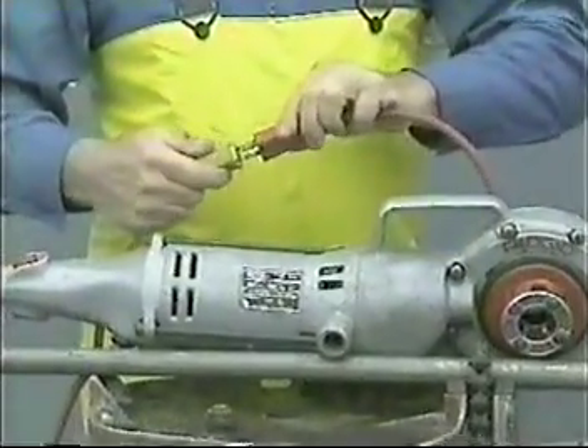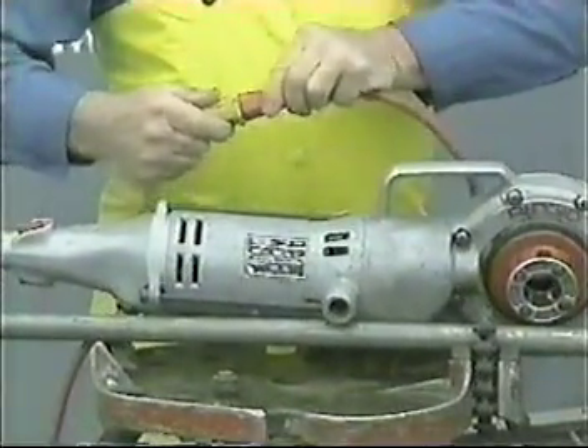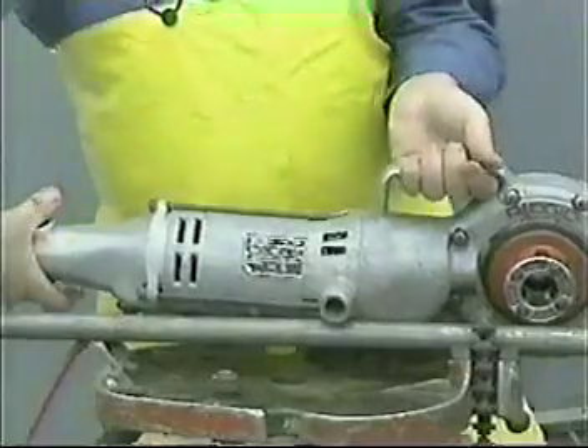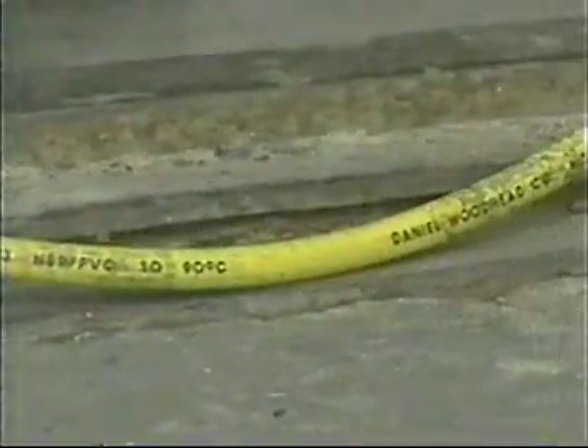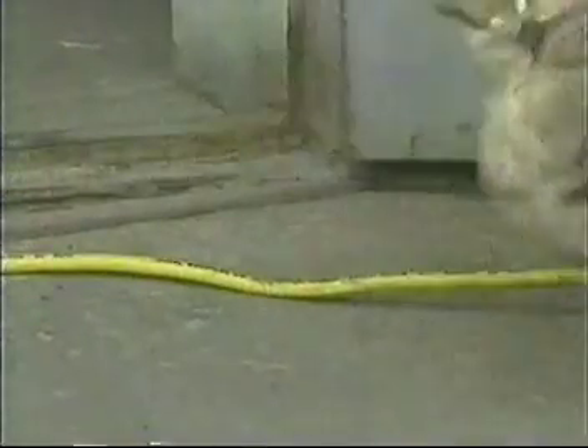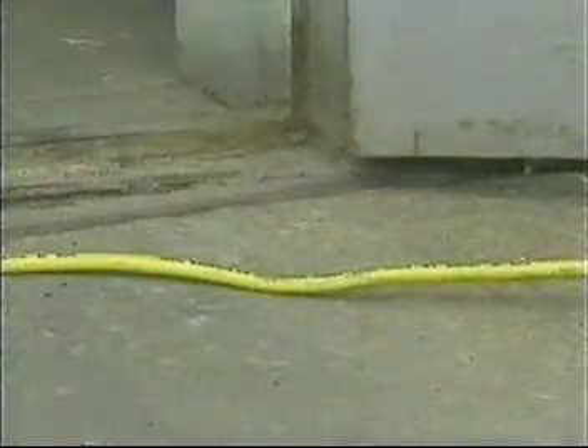When an extension cord is required for portable equipment to be used at a distance from its source of electricity, it should be carefully positioned to prevent accidental damage and properly sized to carry the required amperage. Extension cords are intended for temporary use only. Another electrical safety measure that is often overlooked involves the use of undersized conductors and the overloading of circuits. Both of these conditions can cause overheating and ultimately result in fire.